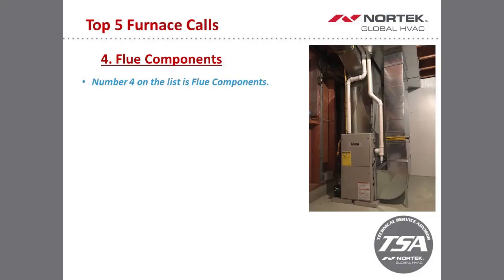What I'll remind you is that the flue pipe, especially, it doesn't really matter for the intake, but the flue pipe has to be pitched back toward the furnace. This will ensure that any rainwater that you would have from outside, or more importantly, the condensation that will be generated with the high efficiency furnace, all drains back to the furnace. Because if the flue pipe is not sloped back, you'll end up stacking water or condensation in the flue pipe, and you'll end up eventually tripping a pressure switch on the furnace. So what we have in the install instructions is a 1/4 inch per foot slope back to the furnace.